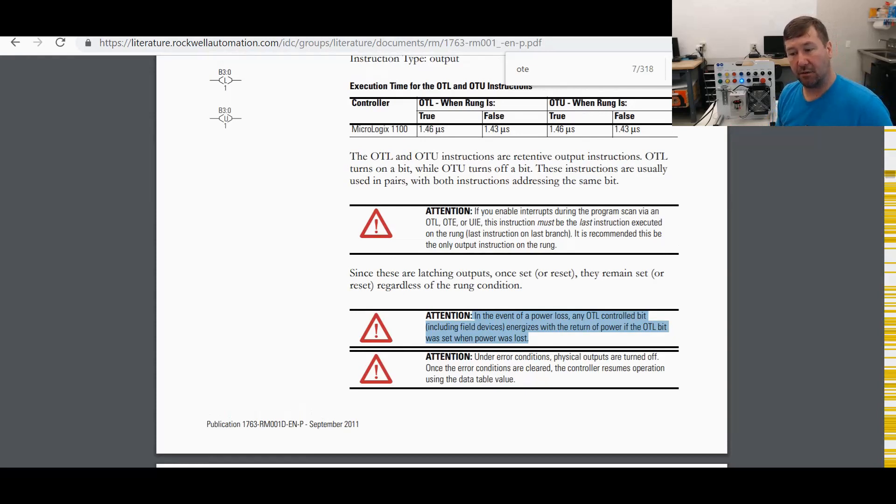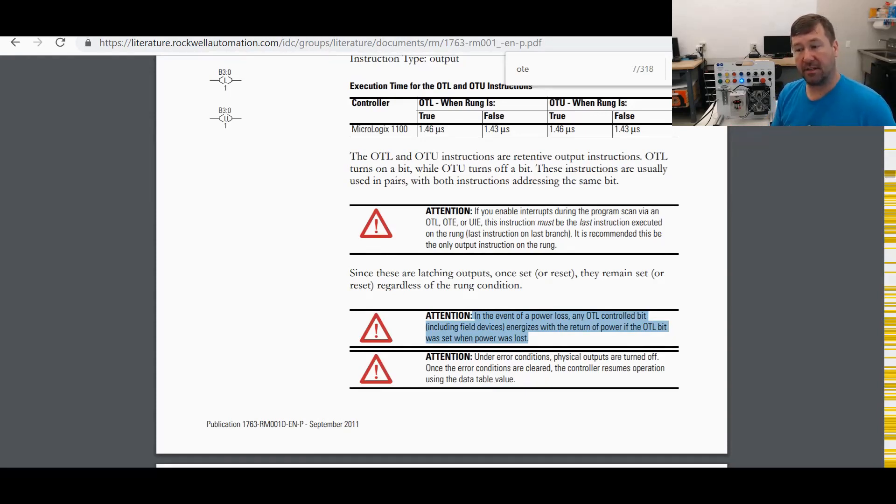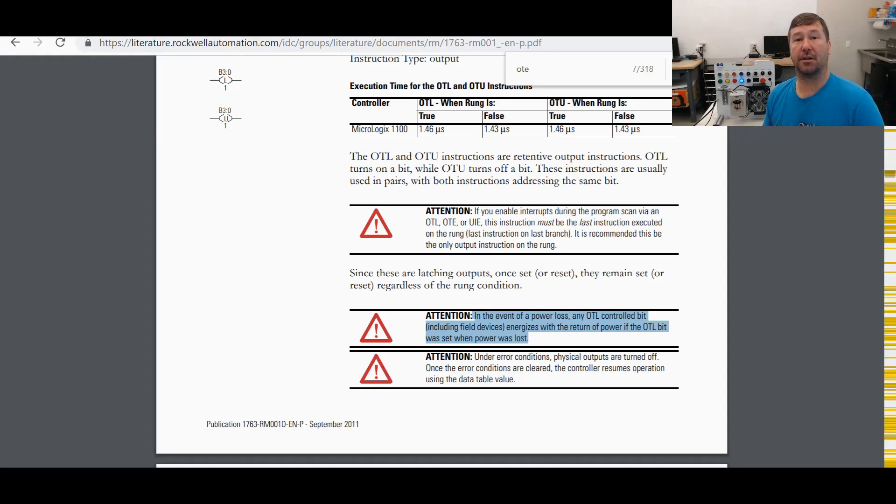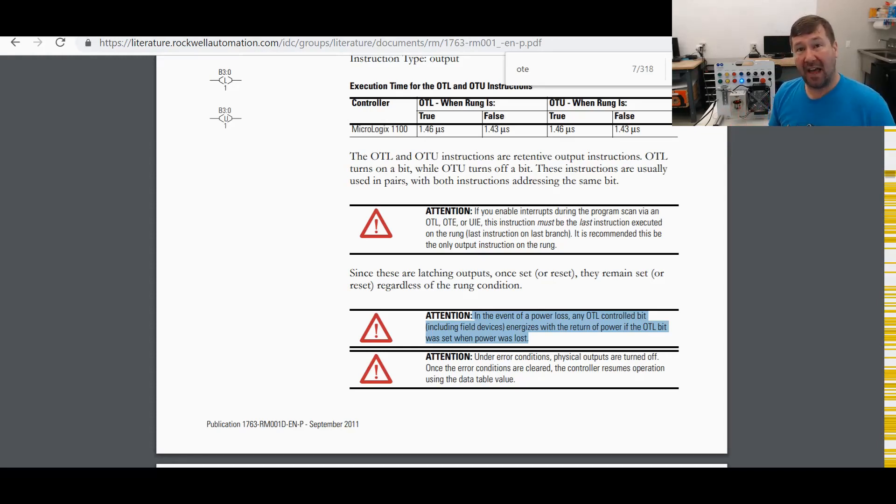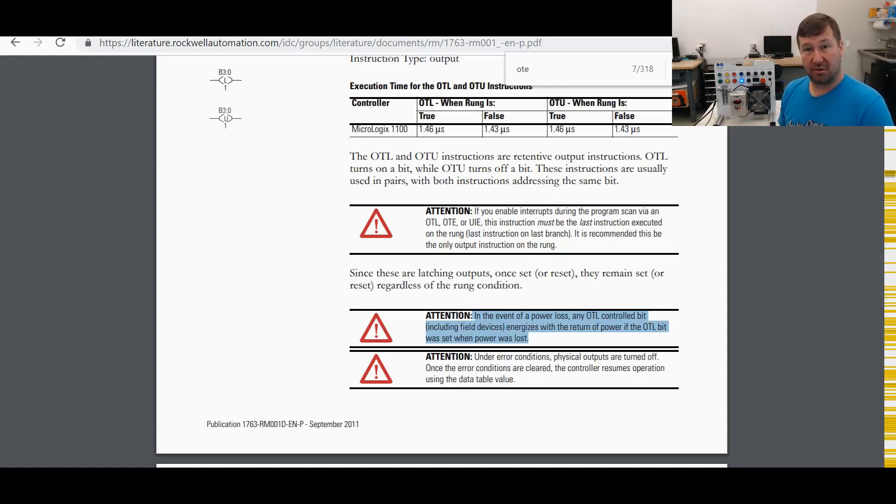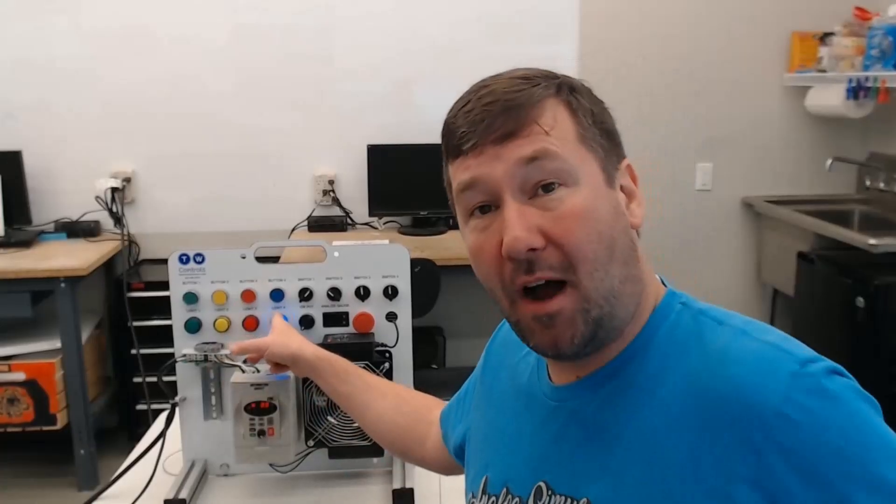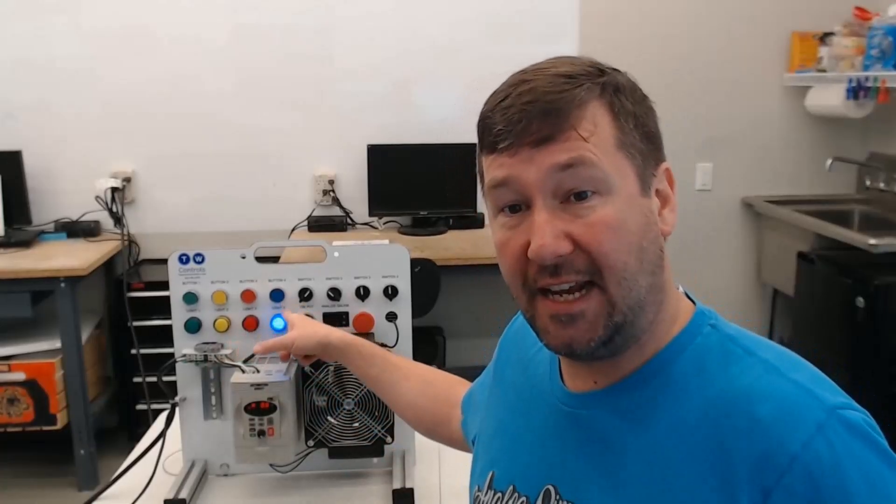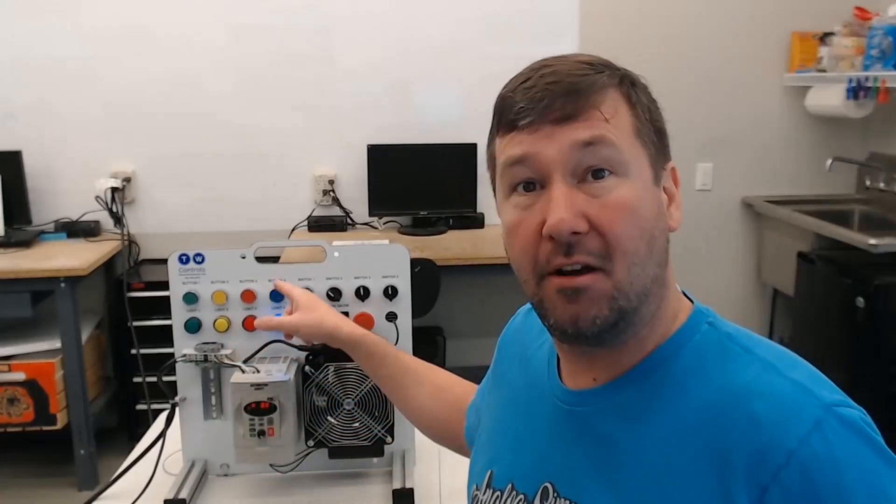energizes with the return of power if the OTL was set before a power loss. In other words, the pre-scan does not affect an OTL or an OTU instruction. That is why our blue light stayed on when we cycled power.